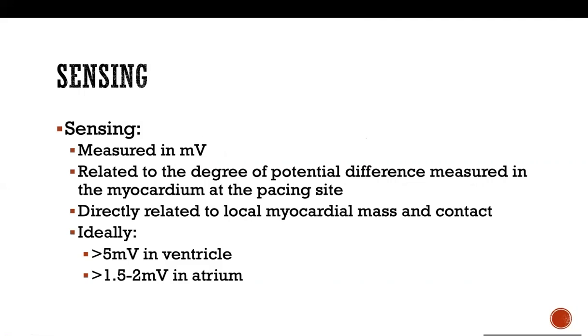So measure the voltage of the electrical signal coming from the myocardium. We usually measure it in millivolts. The normal in the ventricle, because it's the majority of the myocardium, has higher voltage. So ideally you need to have more than 5 millivolts if the lead is in the ventricle. In the atrium, it's a smaller portion of the myocardium, so you don't need a high voltage. So 1.5 or 2 is acceptable, that you have a good contact with the myocardium.